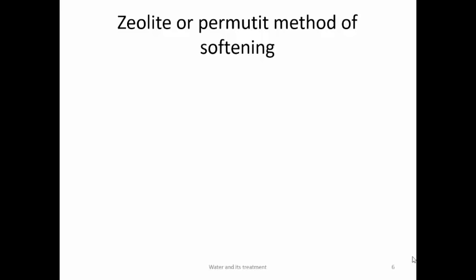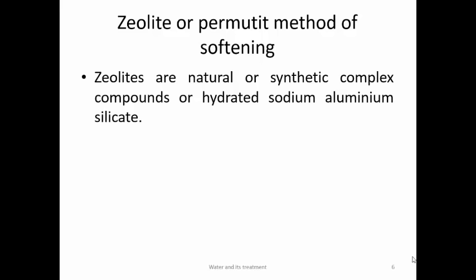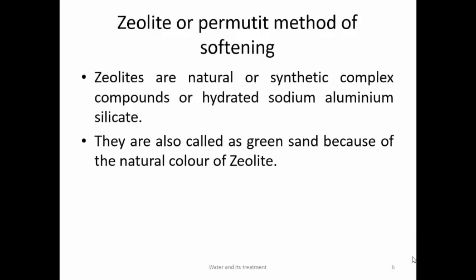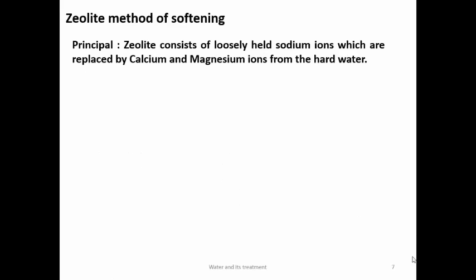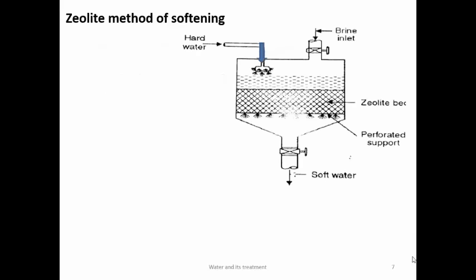Next is the zeolite or permutit method of softening. Zeolites are natural or synthetic complex compounds — also called hydrated sodium aluminium silicate — and are also called green sand due to their natural color. The principle is that zeolite consists of loosely held Na⁺ ions which are replaced by Ca²⁺ and Mg²⁺ ions present in hard water. The formula of zeolite is Na₂O·Al₂O₃·xSiO₂·yH₂O, abbreviated as Na₂Z. Since calcium is a stronger ion than sodium, calcium replaces sodium, and Ca²⁺/Mg²⁺ are absorbed on the zeolite, while the water is freed from them.